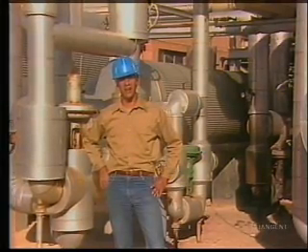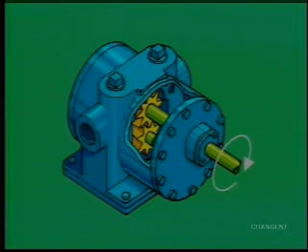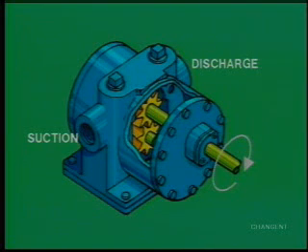External gear pumps can operate in either direction without any special modification to the pump. If you look at the shaft's rotation, you can determine an operating pump's suction side. Keep in mind that the fluid is being pumped around the outer edges of the gear impellers, not between them.